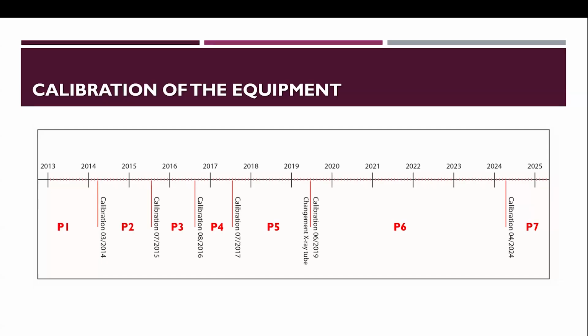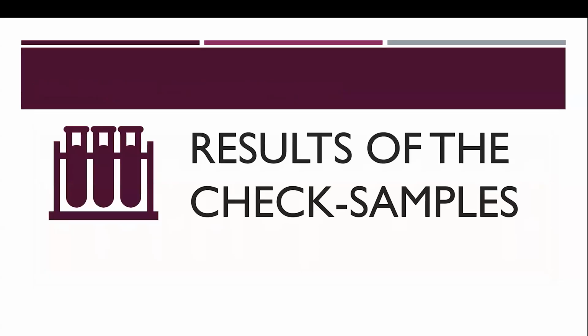To be able to present the results to you, I have given each calibration period a number from 1 to 7, and here only the results from 2 to 7 will be presented by calibration period and year, showing the results of only the certified samples. For the results of the certified reference checked samples, we noted the good precision of the equipment, but a shift in accuracy, mostly related to equipment bias, has been noticed.